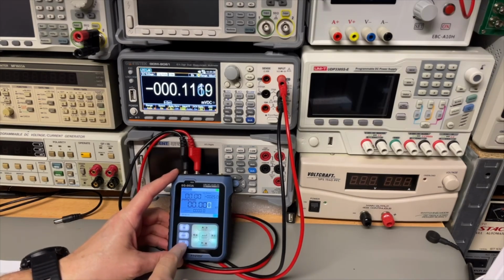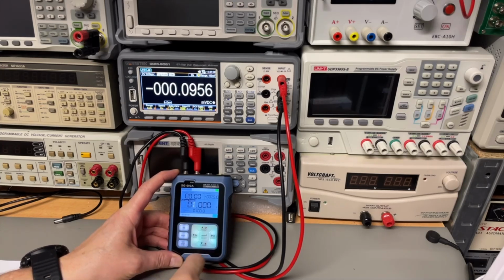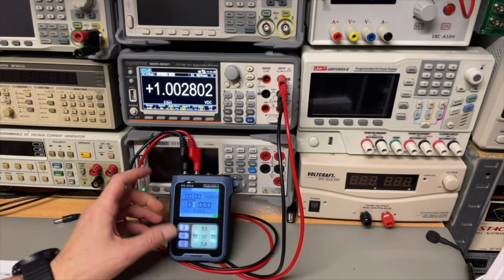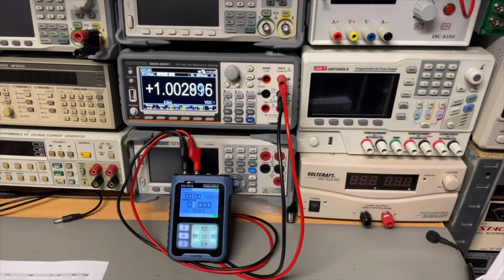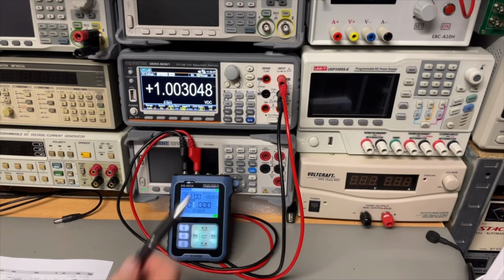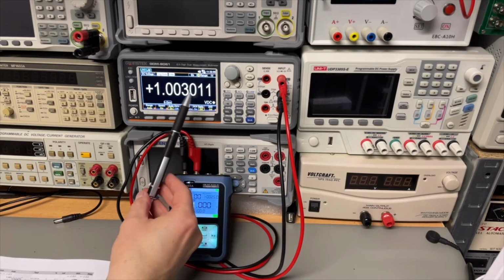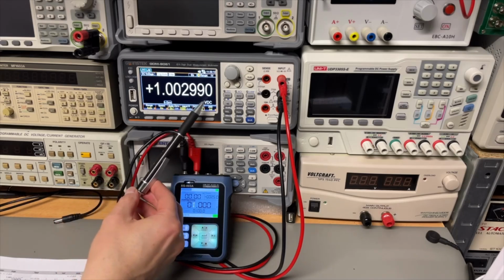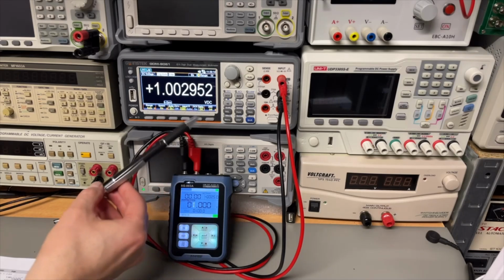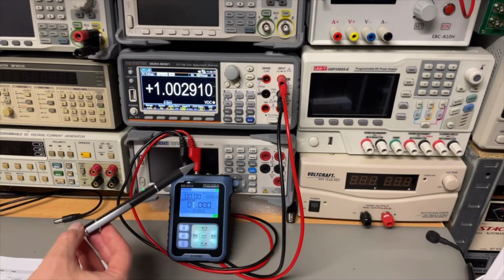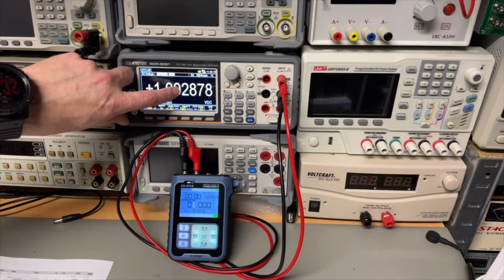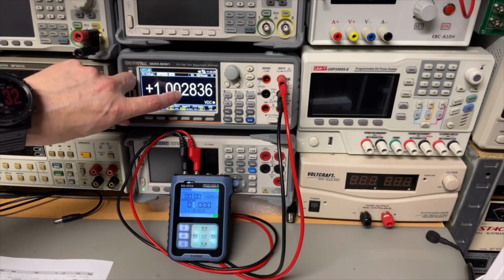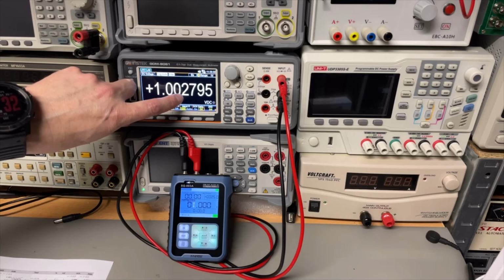We want to switch to output, set it to voltage. Okay, back, now we are set to voltage. I start with 1 volt output on, and let's write down the numbers. Here we can also see that for a 6.5 it's going a little bit down, then correcting itself - it's going up and down, but as long as it doesn't hit the 5, it is within specs.